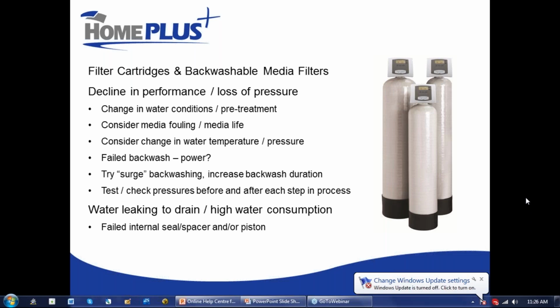You should have a pressure gauge before and after each one. As you start to experience pressure loss, you should be able to read those gauges and quickly determine which step in that process is causing the pressure loss, or potentially it's just a combination of multiple all starting to hit their peak contaminant loading, and in the case of a cartridge needing to be replaced or a media filter needing to be backwashed. We should always consider changes in our water conditions that may relate to the onset of that problem.